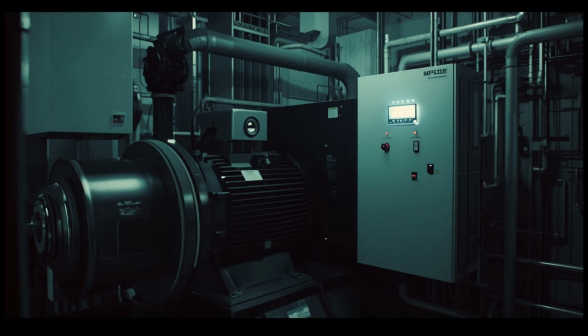The principle behind this quiet cabinet is simpler than its name might suggest. Ordinary electricity arrives at a fixed, unchanging frequency, and a motor left to run directly on that unmodified power would have little choice but to spin at a single, constant speed, running full tilt whether the building needs a great rush of air or only the faintest trickle. The variable frequency drive changes this entirely, taking in that fixed electrical supply and reshaping it, adjusting the frequency of the power delivered to the motor in small, precise increments, and in doing so, adjusting the very speed at which the motor and the great fan wheel connected to it choose to turn.